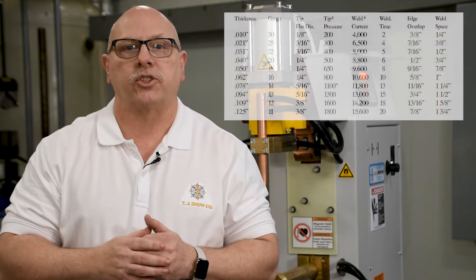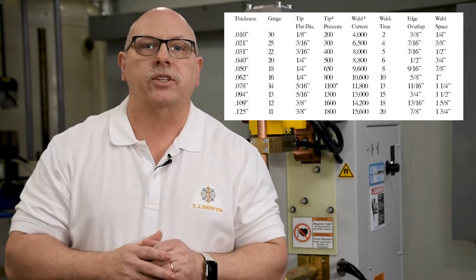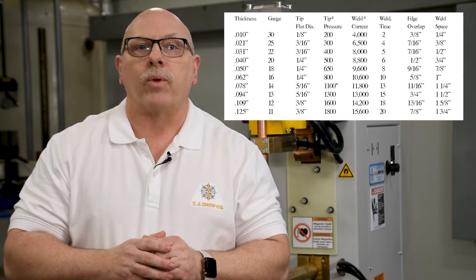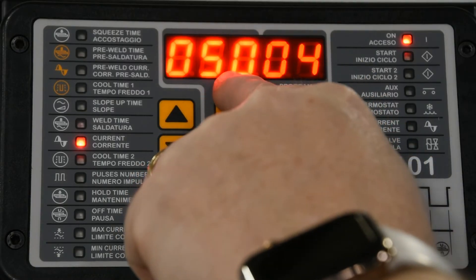The next step is to set the welding transformer tap switch, if provided, to the lowest setting. With these steps done, we can now program the weld controller based on the chart recommendations. We should already have the squeeze function at its maximum value. The recommended weld time for 18 gauge mild steel is 8 weld cycles. Depending on your control's feature set, current may be programmed in amps per the chart callout — 9,600 in this case. However, I recommend starting at around 10% below this value and then increasing from there based on weld tests. If you are programming in percent current, also known as heat percent, set this value at 50% to start.